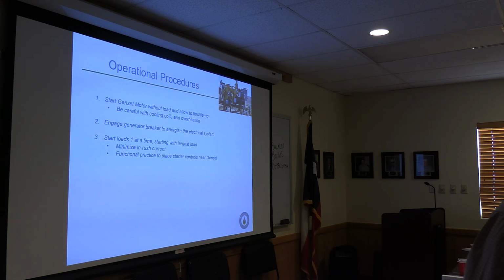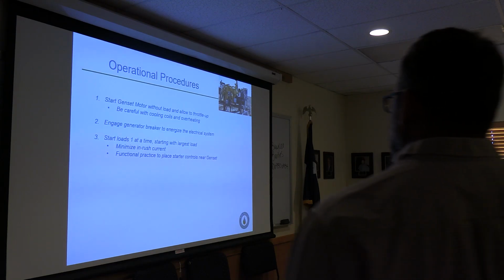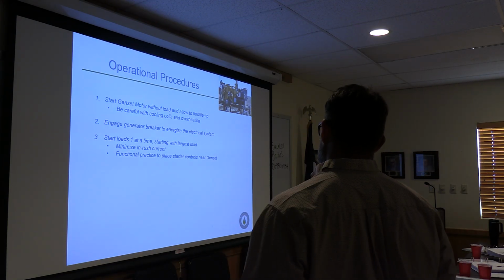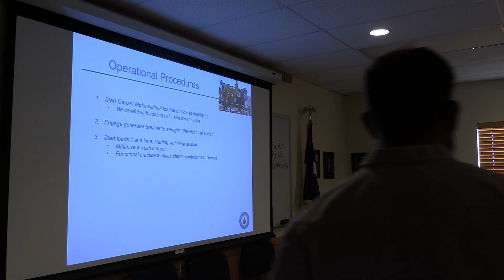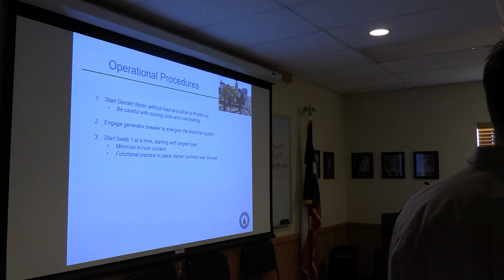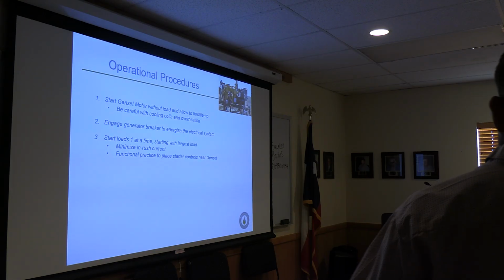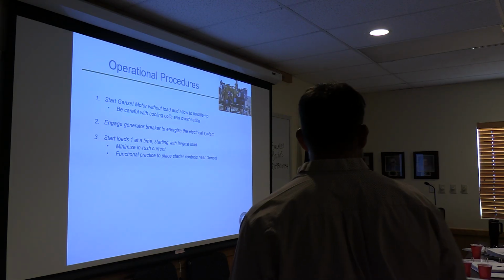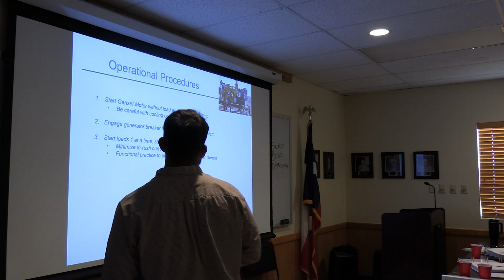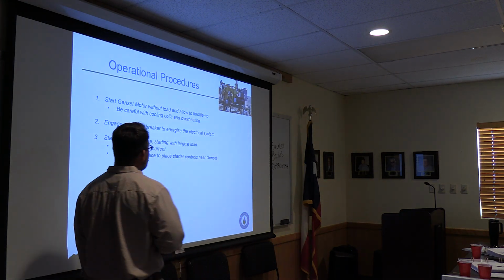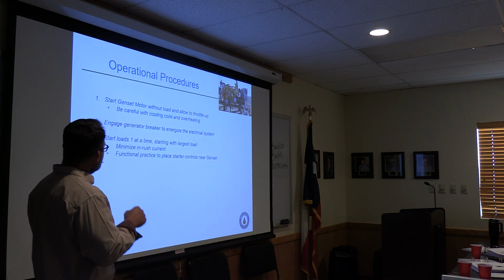You start one load at a time, starting with the largest load. Ideally, the largest load is closest to the genset, meaning less cable to carry the power there, and it's also likely the one you'll run most often. So sometimes if you're only running one, it'll be the one right by the genset.